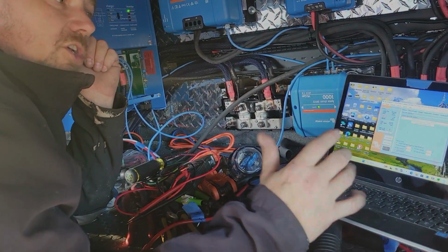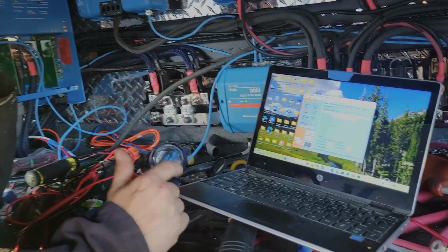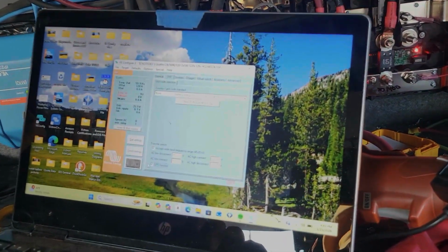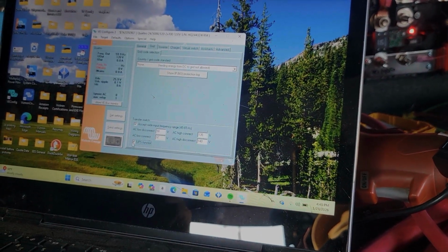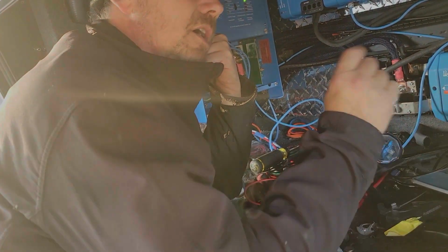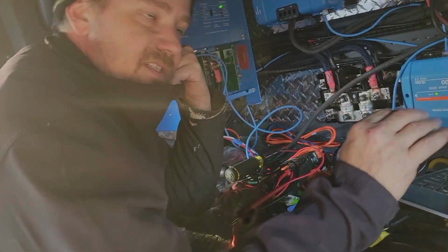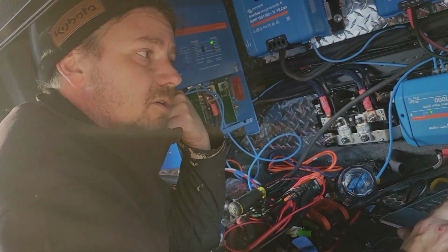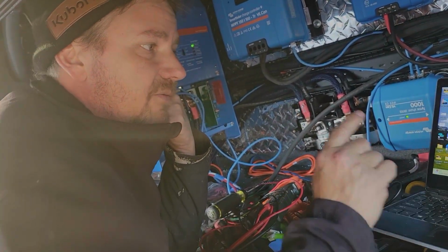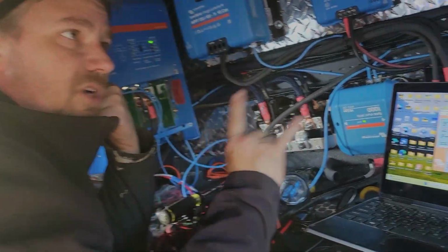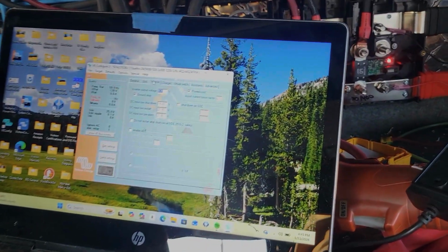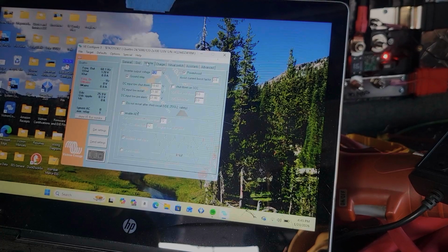But when you have a good generator, like what this has in it, that's an inverter-based generator, we will enable the UPS function because your generator should be able to provide us with a good 120 volt output at a steady 60 hertz, because it's an inverter-based generator. Okay. So we will have that enabled, and now your transfer switch will operate in 10 milliseconds. Got it. Because of the UPS function.